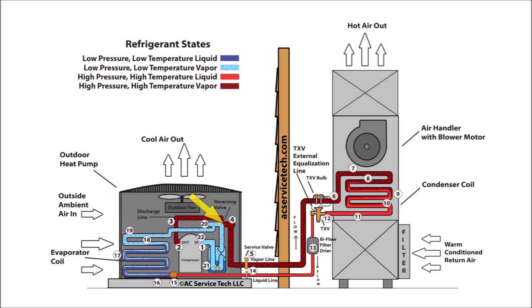This superheated vapor travels through the reversing valve at step four, and it heads towards the vapor service valve. At step five, we have the high pressure, high temperature, superheated vapor traveling through the vapor service valve and heading into the indoor coil. Since we're in heat mode, it's going to be referred to as the indoor condenser coil.